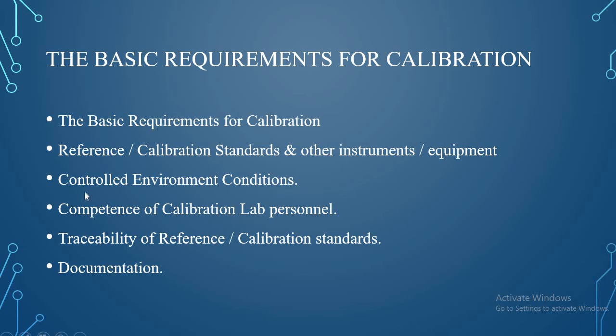Then next is controlled environmental conditions. Now in the case of various engineering fields, the measurements of various parameters also depend on the environmental conditions. So when we calibrate the equipment or instrument, we have to maintain some basic conditions so that the instrument can be calibrated properly. And next is competence of calibration lab personnel. The person who is going to calibrate should be competent for that procedure.